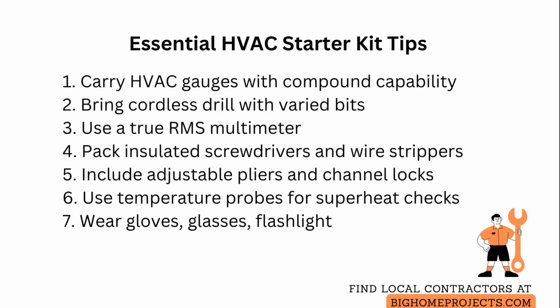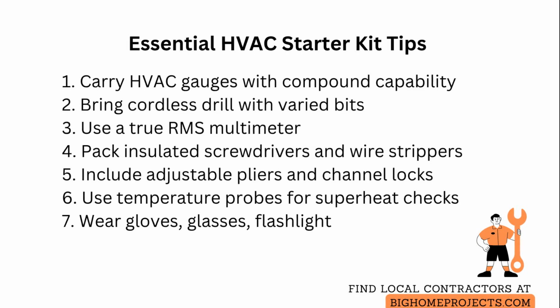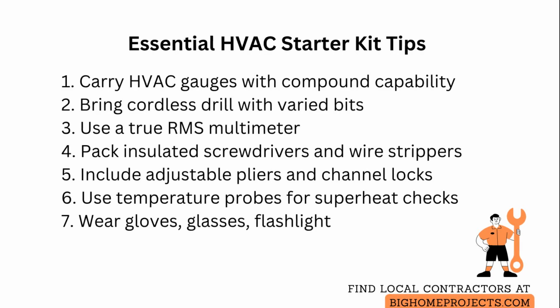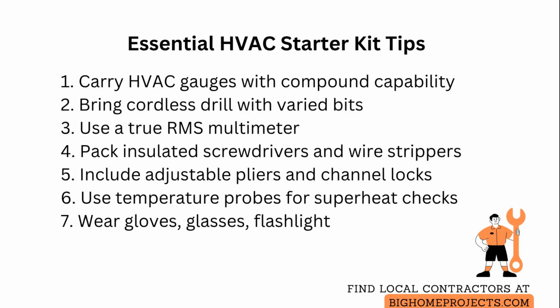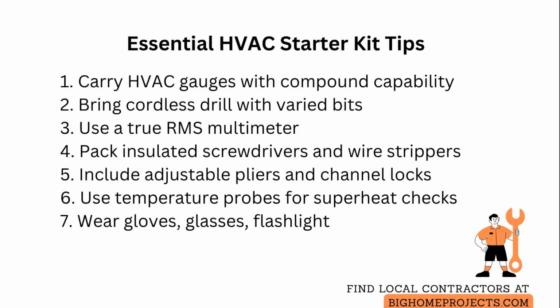shorts while working on control boards, and a set of adjustable pliers and channel locks help with flare nuts and refrigerant line fittings. Bring temperature probes that can clip to ducts and probe ambient air temperatures, and use them to perform sensible superheat and subcooling checks while noting indoor and outdoor wet bulb temperatures if needed.